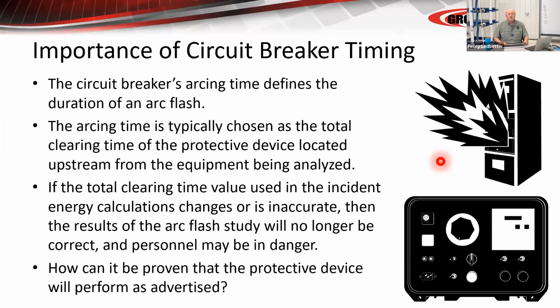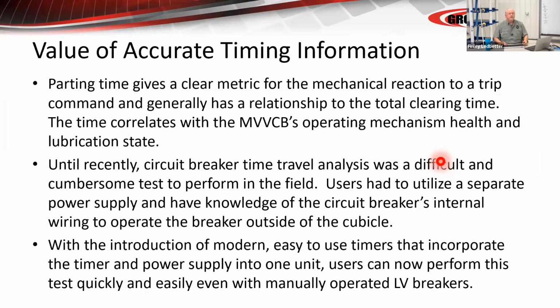So make sure you're either looking at first trip timing, or you're looking at overall clearing time, or you're running a transducer and getting the whole package. But make sure you're using some timing information to determine if your maintenance interval is right and if your lube is right. If you don't get a good metric there, you don't really know.